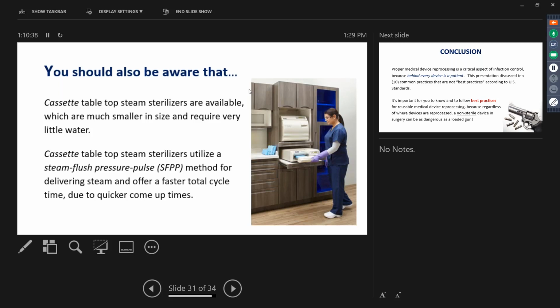So we run all the eye instruments in that FDA cleared cycle, 270 degrees for 3.5 minutes. It's 6 minutes start to finish. We take out the cassette, take it to the operator. Yes, when we open it up it's completely wet, but that's an FDA cleared cycle, and we're using it.